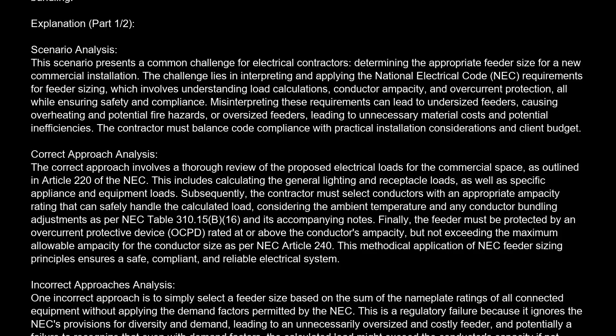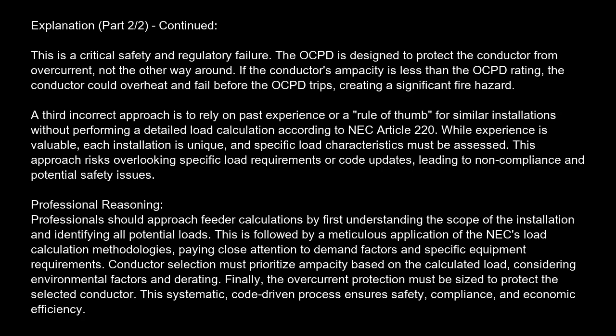Another incorrect approach is to select a feeder size based solely on the overcurrent protection device rating, without verifying that the conductor's ampacity meets or exceeds the calculated load. This is a critical safety and regulatory failure. The OCPD is designed to protect the conductor from overcurrent, not the other way around. If the conductor's ampacity is less than the OCPD rating, the conductor could overheat and fail before the OCPD trips, creating a significant fire hazard.